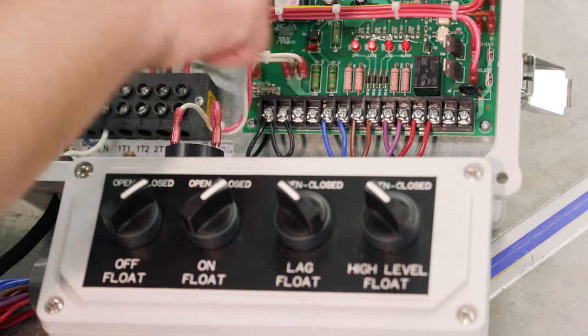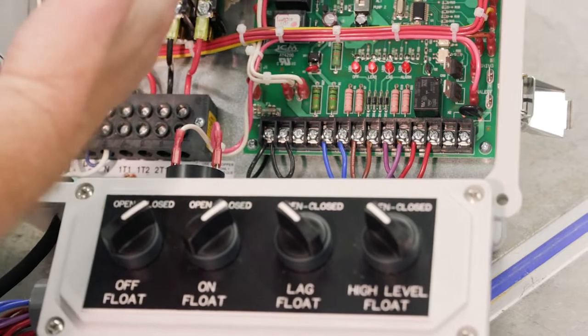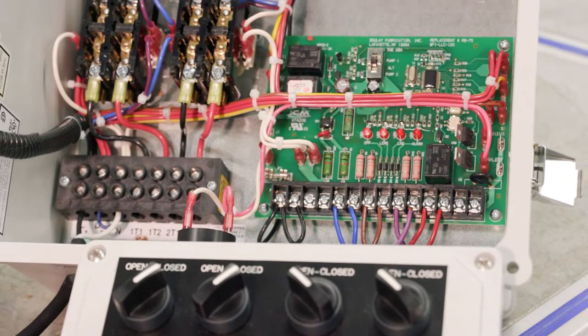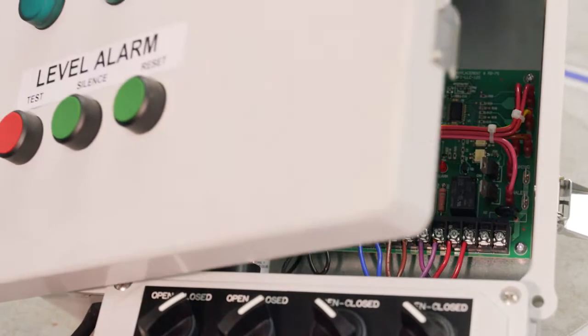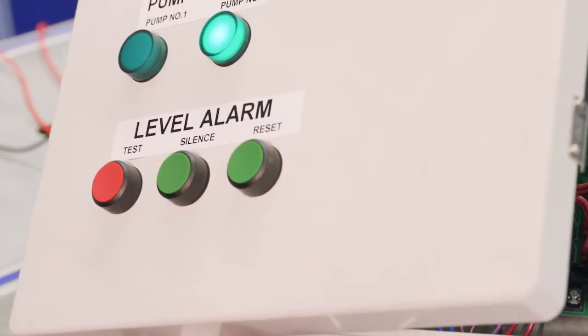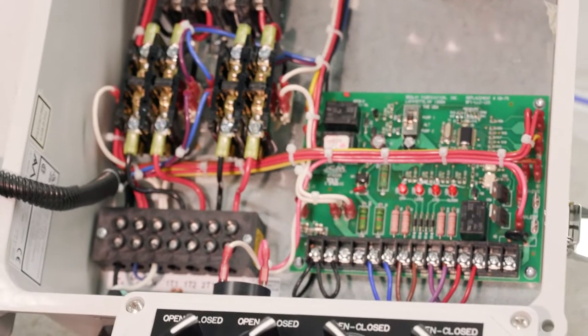LED turns on, contactor pulls in, we can hear that. And we can see that pump two is running. So light is on, pump two is running.